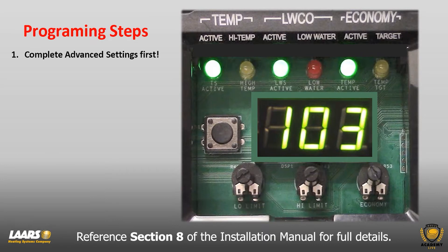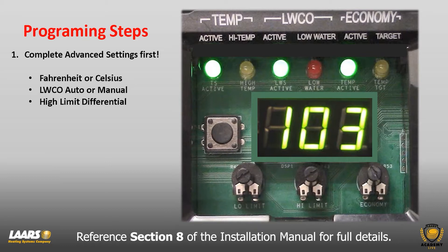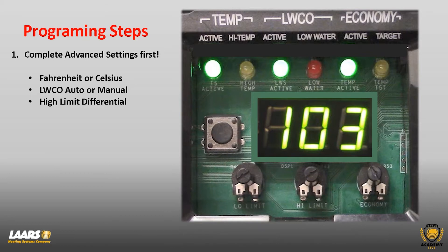Step one: complete the advanced settings first. Under advanced settings, you can change from Fahrenheit to Celsius, change your low water cutoff from auto reset to manual reset due to local codes, or change your high limit differential. The high limit on this boiler is an auto reset. Using the example of 200 degrees with a defaulted differential of 30 degrees, at 200 degrees the boiler shuts off but at 170 it would refire.